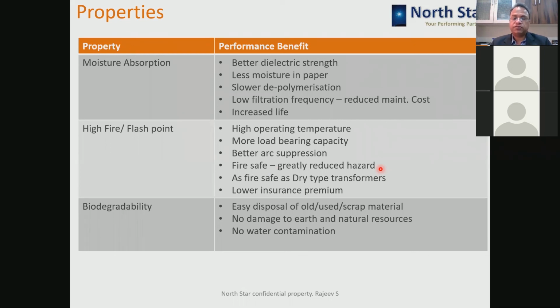Okay, since your transformer is fire safe, chances of fire accidents are less, so the insurance premium of the factory or premises is lower, so there also you are saving indirectly. Okay, biodegradability is the third property. So the disposal of old, used, or scrap material is easy. You're not causing any damage to the mother earth and natural resources, and the water bodies are also not getting contaminated because of leakages and seepages into them. So you are helping the environmental sustainability of our nature and our earth. So that is a big contribution. The biggest contribution compared to all of the above is because of biodegradability.